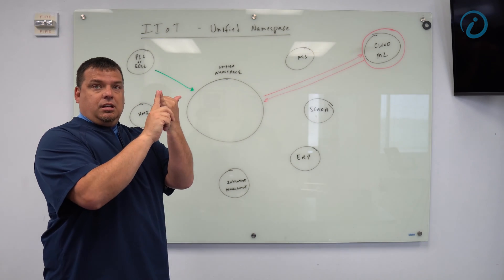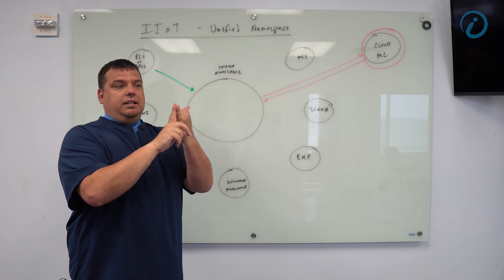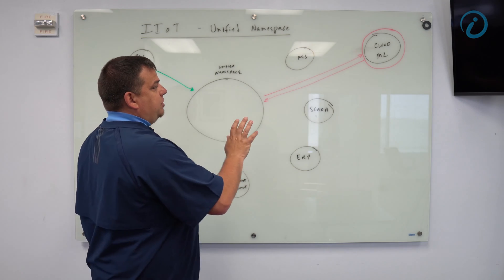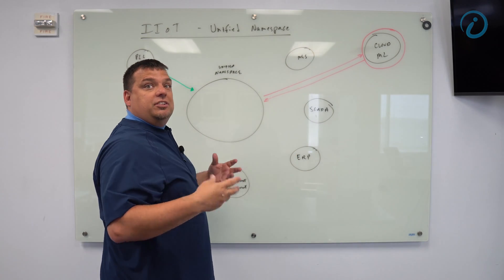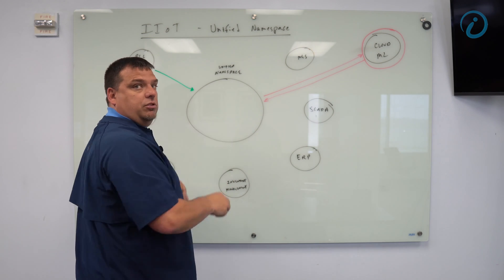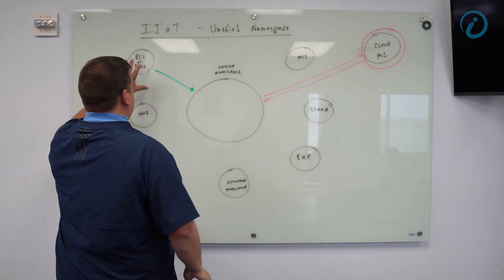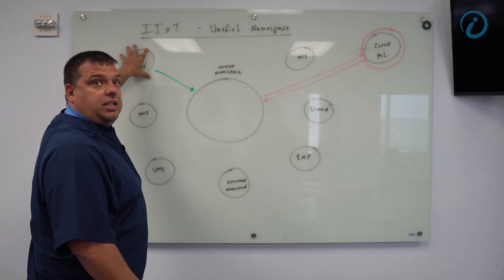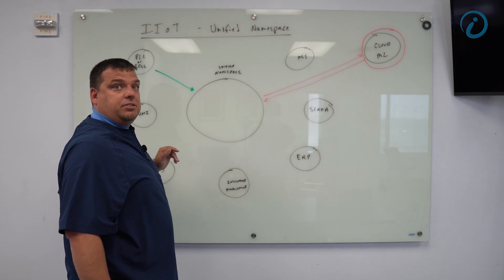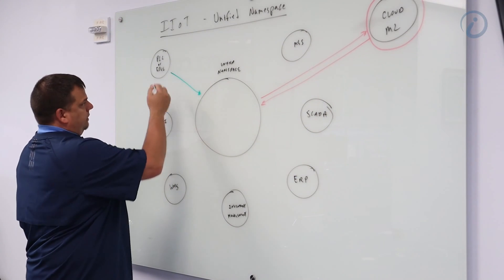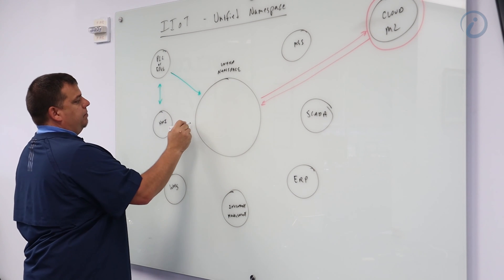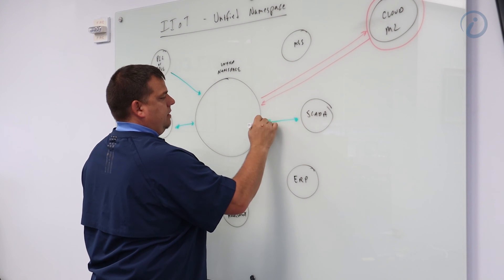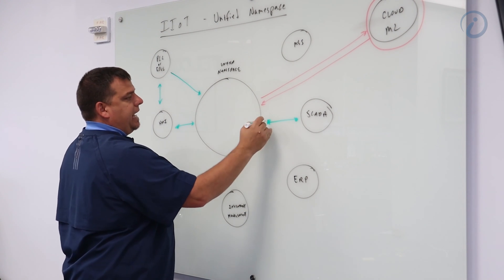In order for us to scale — enterprise implementation — and to fully leverage IIoT and Industry 4.0 concepts and digitally transform a business, we have to change this in terms of the way we connect applications together. We do that by creating a Unified Namespace. We treat all applications, everything in the plant and on the plant floor, as a node in the system. Our PLCs publish their data into the Unified Namespace, and the SCADA system and HMI get their information from the Unified Namespace.